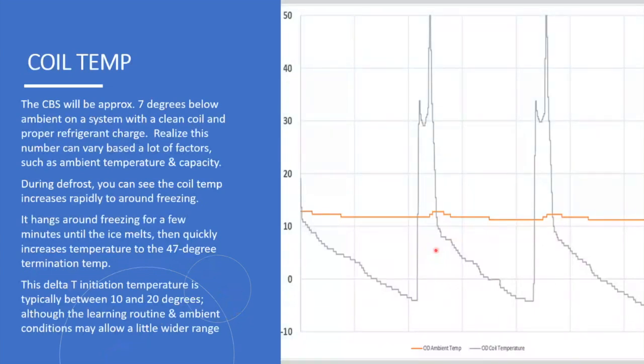So how those two sensors work together. The orange line is ambient, and the gray line is what the coil temperature would be seeing. This is through some runtime and two defrosts. What happens is, as the coil frosts up, the coil will get cooler and it'll become less efficient. As it becomes less efficient, that coil sensor is reading a colder temperature. Once that delta reaches a certain point, maybe 10 to 20 degrees delta, it would trigger a defrost. A normal operating system without frost would be about 7 degrees delta.